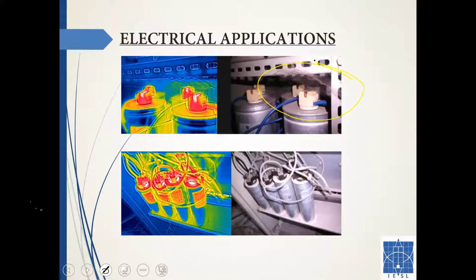This is research we do these days with some of the manufacturers, and the capacitors are really interesting. And like I said, your capacitors, like each and every component in your system, undergo thermal cycling. They get current fluctuations, they get ambient temperature fluctuations, and they have to tolerate all kinds of abuse. So generally speaking, your thermal imaging survey must cover the capacitors, and you need to do the preventive maintenance of the capacitors anyway to minimize these effects.